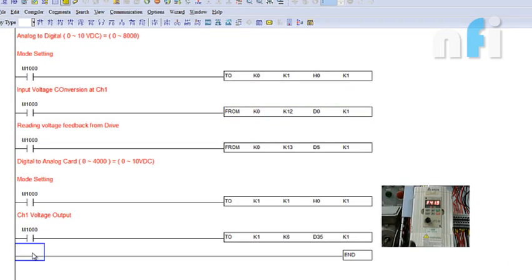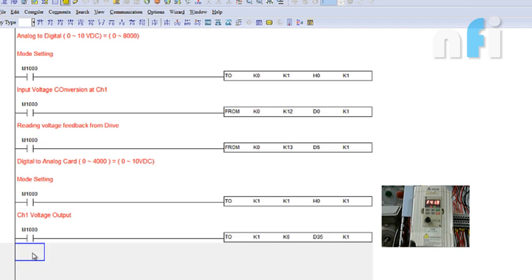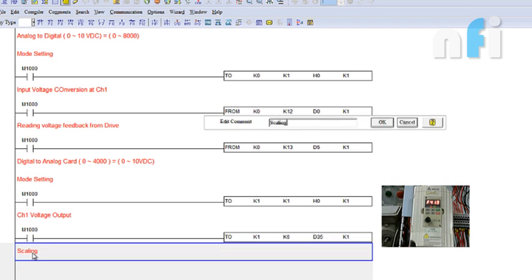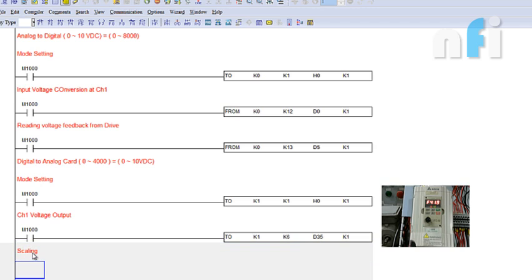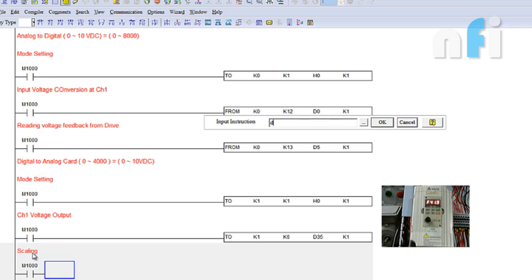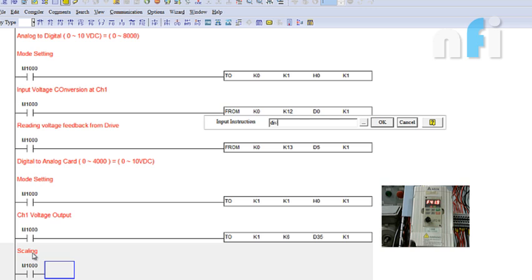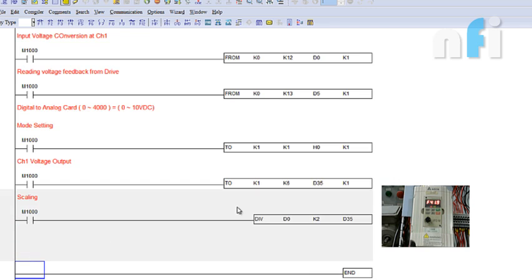Let's do scaling feedback. Here I can make a logic. My value is coming into D0, so I have to divide the range of 0 to 8000 to 0 to 4000, simply divide by 2. So I write DIV, divide D0 by K2, results in D35.